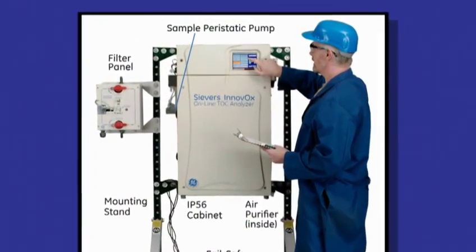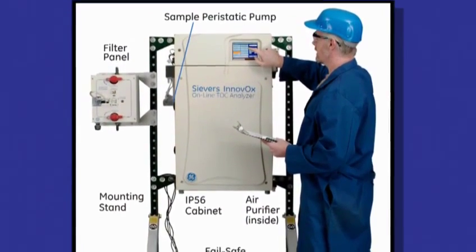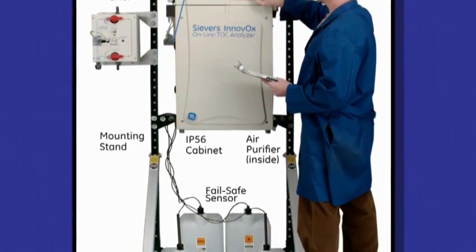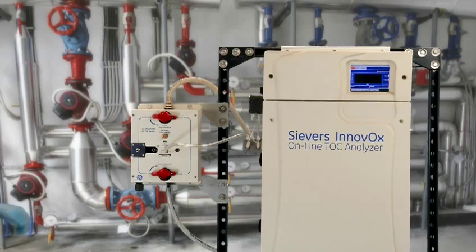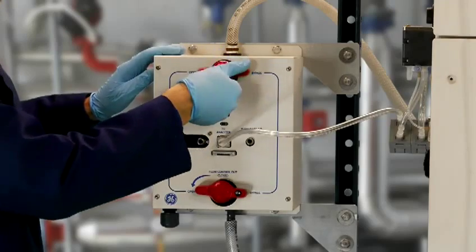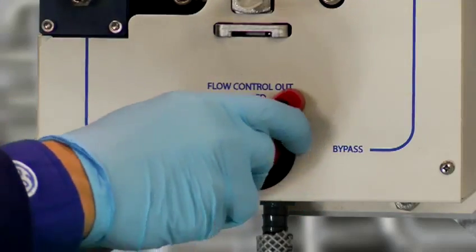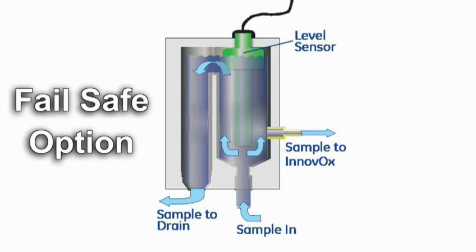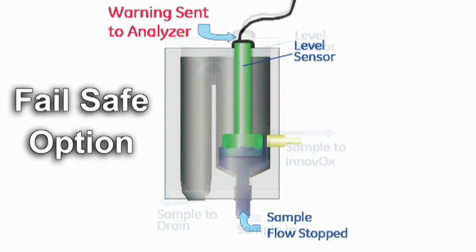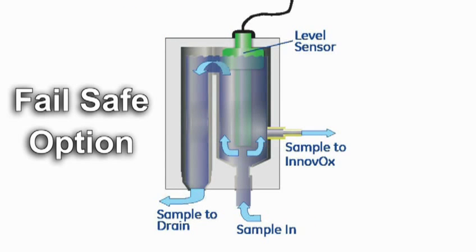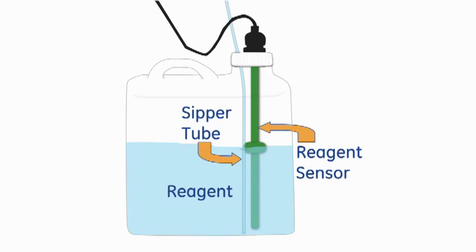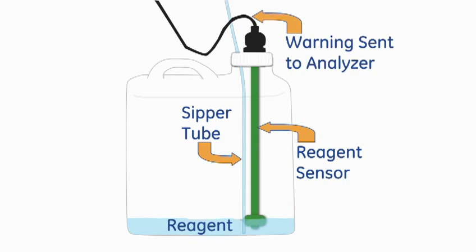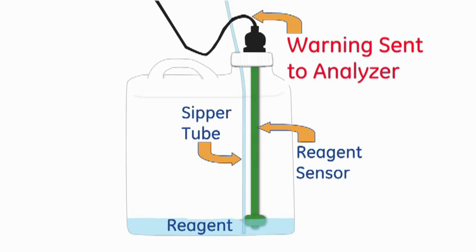We understand that no two waste streams are the same, so we offer various accessories to customize the Innovox for your application. For applications that include suspended solids, the filter panel should be used — it removes large particles before sample analysis and is self-cleaning. The Failsafe option monitors the sample stream, placing the analyzer on standby when flow stops and automatically restarting when flow resumes. It also monitors reagents; if reagents are depleted, the Failsafe feature puts the Innovox on standby and alerts you that maintenance is needed.